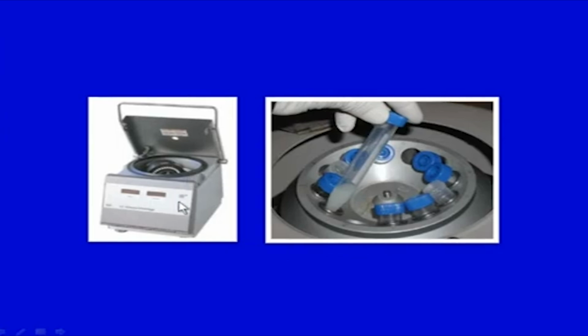They have means to set the speed limits, and according to the rotor you can set the amount of centrifugal force to be applied. Remember, these rotors specify the kind of centrifugal force which can be applied on them, because the material they are made of can only sustain a certain amount of centrifugal force or stress. So, these are all automated centrifuges, and they function well, and they are also refrigerated for biological molecules which can go bad as heat generation might take place.